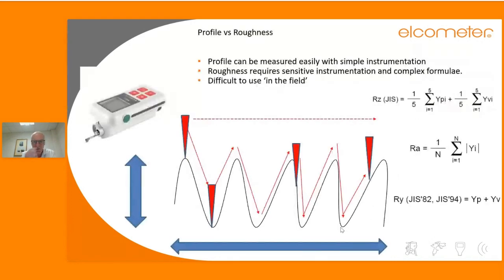If we just look at roughness in a bit more detail, basically that's how the roughness gauge works. We have the MAR gauge there that is roughness, and on the tip of it in the bottom left hand corner you can actually see a stylus, which those of us, including myself, who are old enough to remember the old record players with the needle that went onto the record to produce the music. That works in a very similar way.